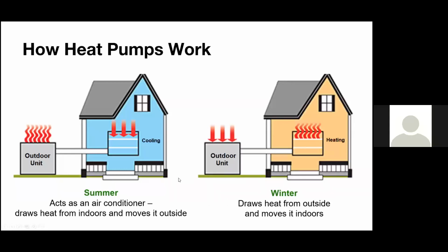So another example, thinking about your freezer, that little heat pump you have in your refrigerator is able to extract heat from that freezer and heat your house that way. So the one thing that happens as it gets colder is we have a harder time getting heat. You have to put a little bit more power into it, and we tend to get a little bit less heat for every kilowatt of power that we put into it. So we'll actually talk later on something called a COP, which is something on the efficiency side and what might happen as it gets colder.